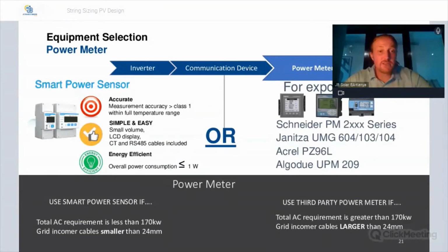So the Smart Power Sensor, if you look at the gray on the bottom, has a size limitation. Basically, the total AC requirement should be less than 170 kilowatts. Also, the grid incomer cables should be smaller than 24 millimeters. That's because of the size of the CTs. Now, if you have a larger project, larger than 170 kilowatts AC, or if the grid incomer cables are larger than 24 millimeters, you will need to use a third-party power meter. There's a small list on the screen, and we have more webinars for this in more detail. So the point of this is you have to choose your inverter, you choose your communication device, and you choose your power meter.